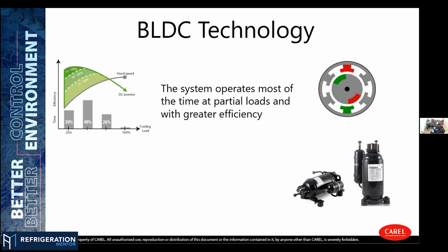And considering that BLDC is a technology that was made to be variable, it is mandatory to have an inverter or a driver like this one to make the compressor run, because since we don't need to inject current in the rotor, we need to know exactly the position of this rotor in order to make the magnetic field on the outside.